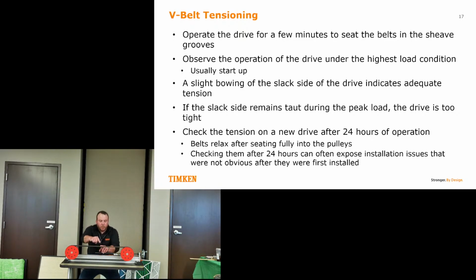And I'm simply going to put this laser as close to it as I can without touching it, and I'm going to pluck it. And you can hear it beep, and I'll get a frequency reading of 54 hertz. I usually do it 3 times. I might get 52 one time, 56 another, and 54, so I take the average. That'll be at 54 hertz, right?